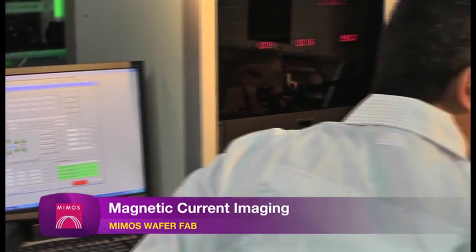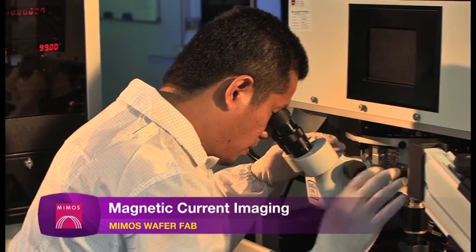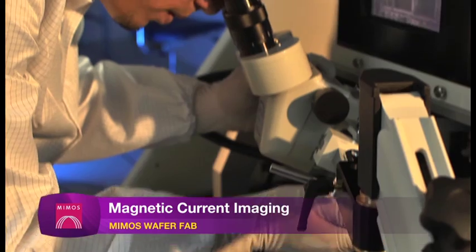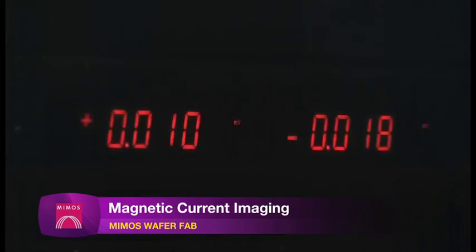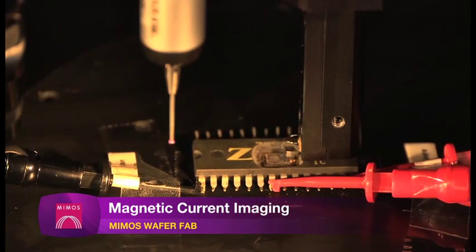The magnetic current imaging system MCI reveals defects such as leakage, short and resistive open. Equipped with two magnetic sensors, SQUID and GMR, the system is capable to detect even weak magnetic fields and determine the failure locations.